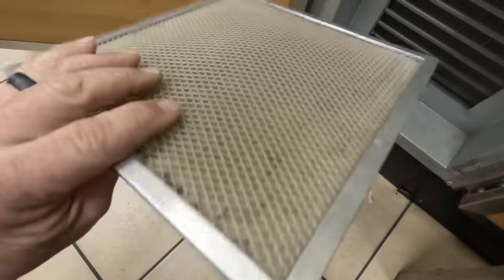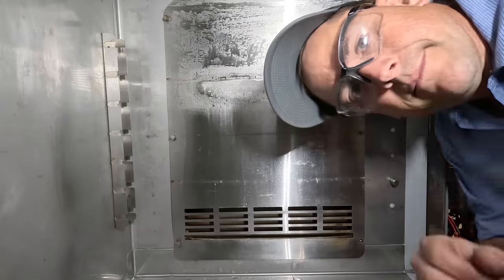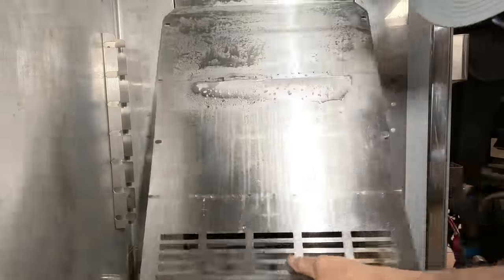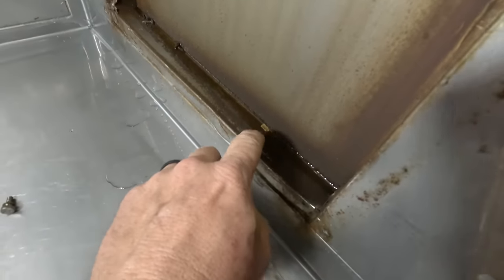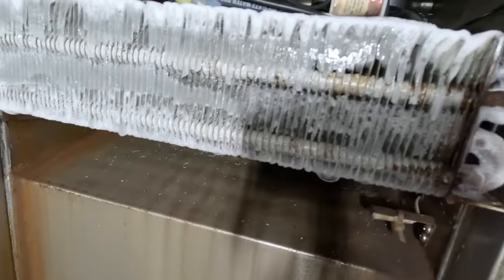Kind of a fancy hygienic type of air filter thing, ain't it? They're getting better at building these, that's for sure. There's the compressor all hidden back in there. Looks like a cap tube system. I can see oil — I bet we got us a leaker.